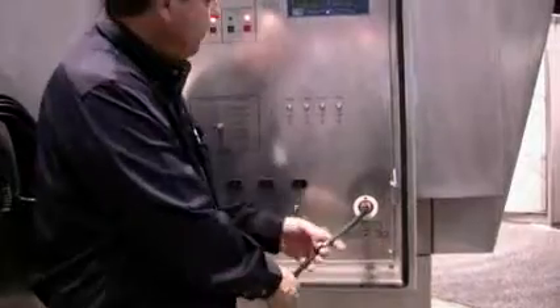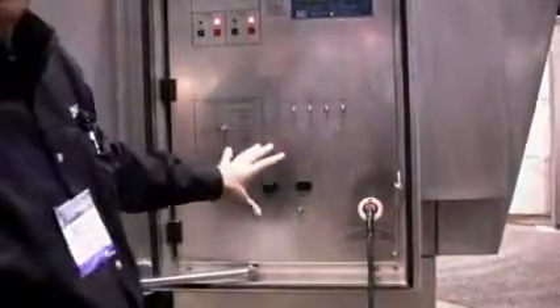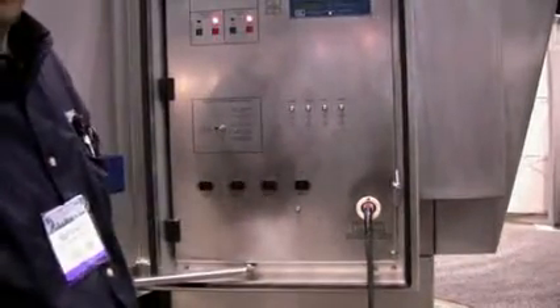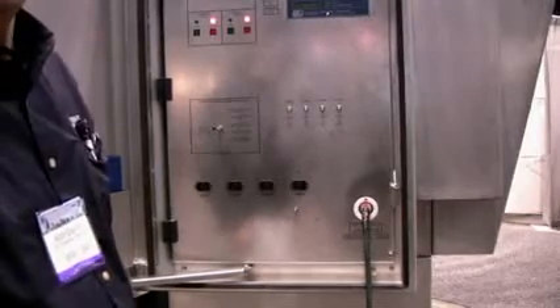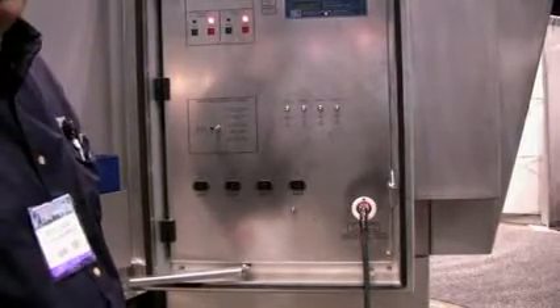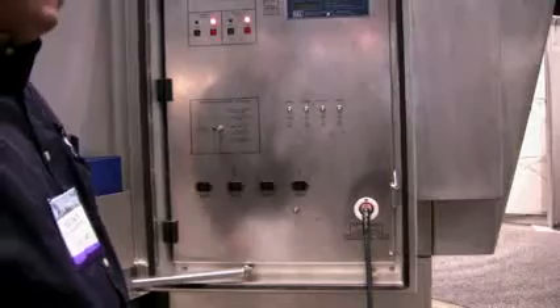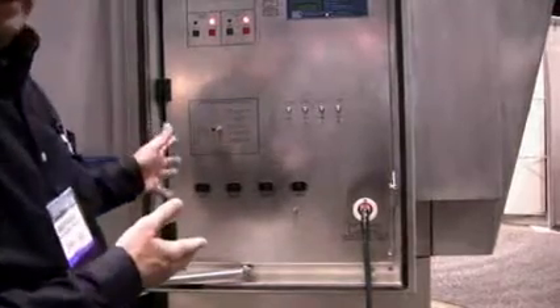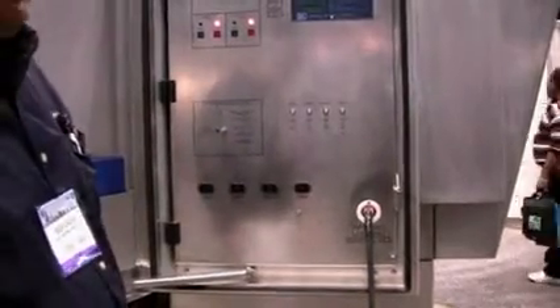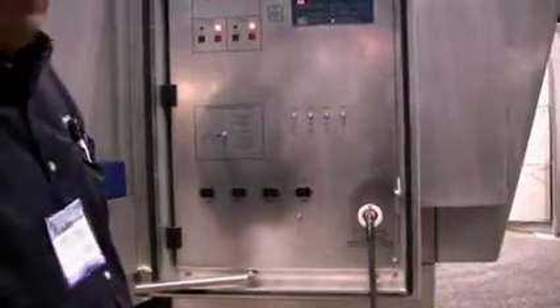Again, you'll notice we have an operate switch. It's in the test position. It allows us to power up the whole control and test the whole unit locally before it's installed, so it can be tested in the yard by the techs and SCADA personnel. So it gets done, it gets tagged, and then the line personnel can take it out to the site and install it.